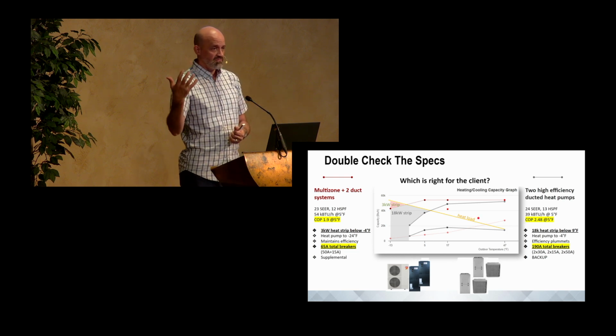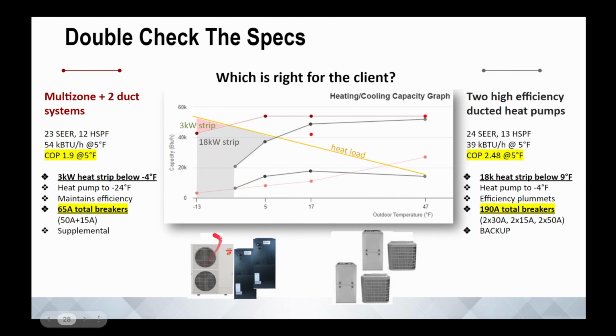It's just a consideration that you have to grapple with when you're paying to size systems, paying for equipment, and then powering it with your solar, your batteries, a generator, however you want to do your resilient solution. On the left-hand side, this red line right here, this single outdoor unit and 2 air handlers is able to maintain 100% at 5 and about 80% at -13. It's going to continue to diminish slowly, but you can see this little 3 kW strip right here that's supplemental heat instead of 18 kW of backup heat.